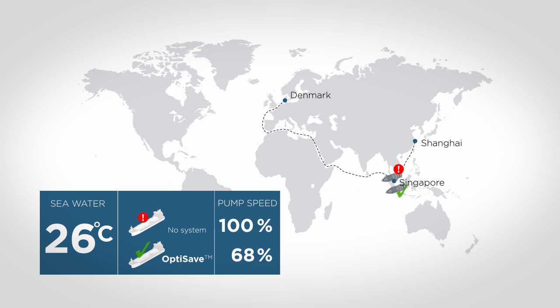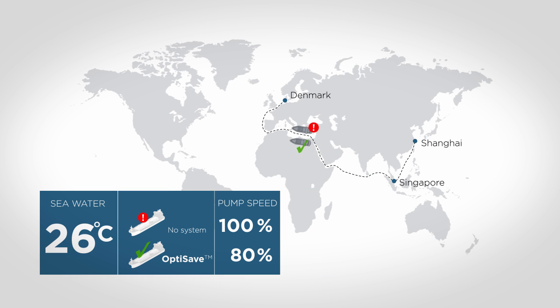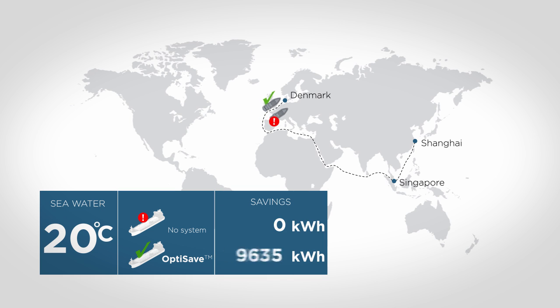When reaching Singapore, the seawater temperature has increased to 28 degrees. At this location the pump speed of the OptiSave system will be 80%, saving from 90 kilowatts to 46 kilowatts. When reaching the Mediterranean the seawater temperature has dropped to 20 degrees. When arriving in Denmark, the accumulated savings achieved by the Desmi OptiSave system is 52,000 kilowatt hours, corresponding to 75% savings.